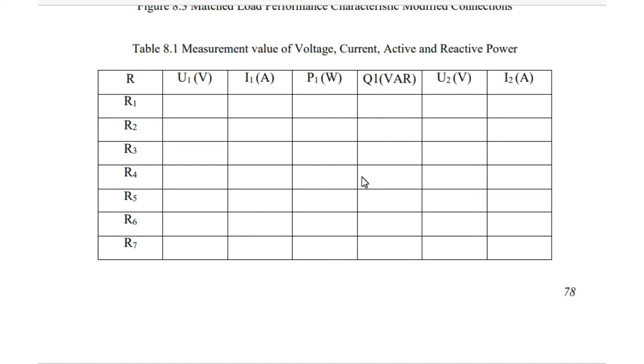You can see it will start increasing, but at a certain point it will almost reach the R4 value. You will see that at R4 the reactive power is minimum, because here the surge impedance loading occurs, maximum power is transmitted and reactive power is almost zero. So we will perform this on the hardware and you will see it in the video.